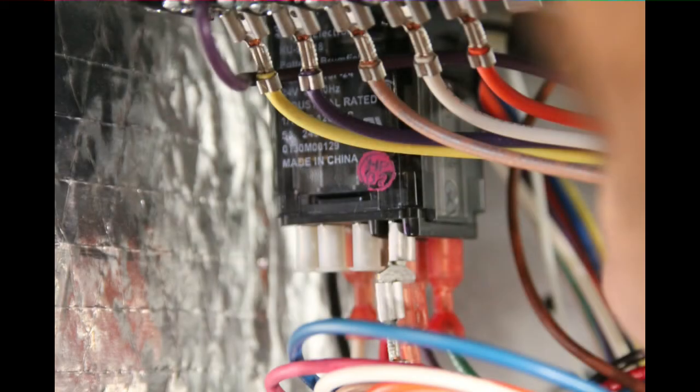Hey guys, we are looking at the inside of a Goodman or Amana ASPT air handler. This is the blower relay that they are using now. They used to use a different type but had a lot of problems with it on the ASPF air handler as well. This new air handler has a little bit of clearness to it like an icebox relay, but it is a double pole double throw, though they're not using one of the poles on this particular machine.